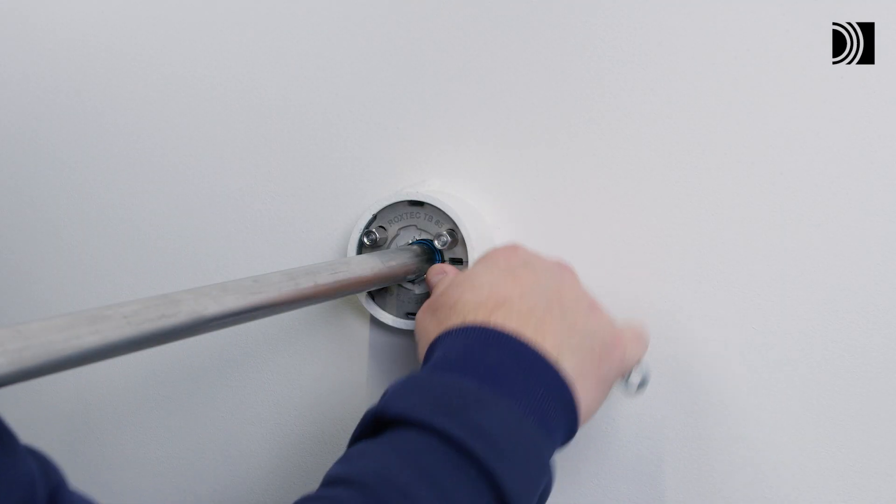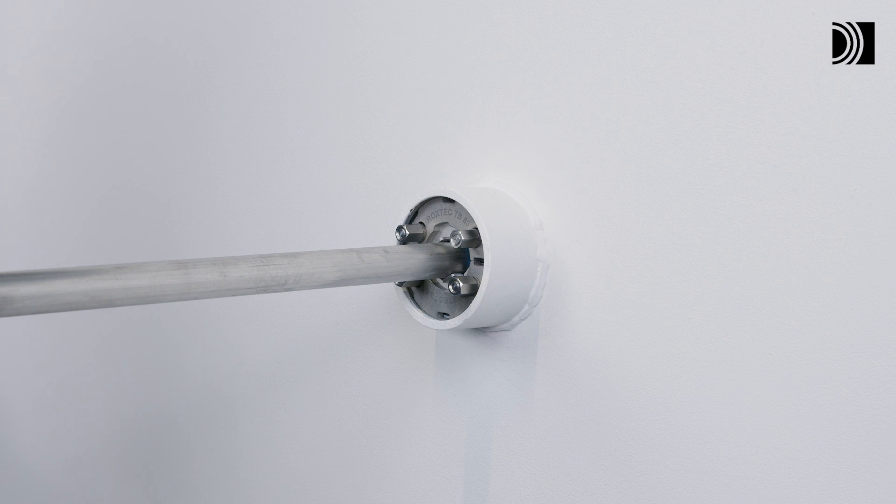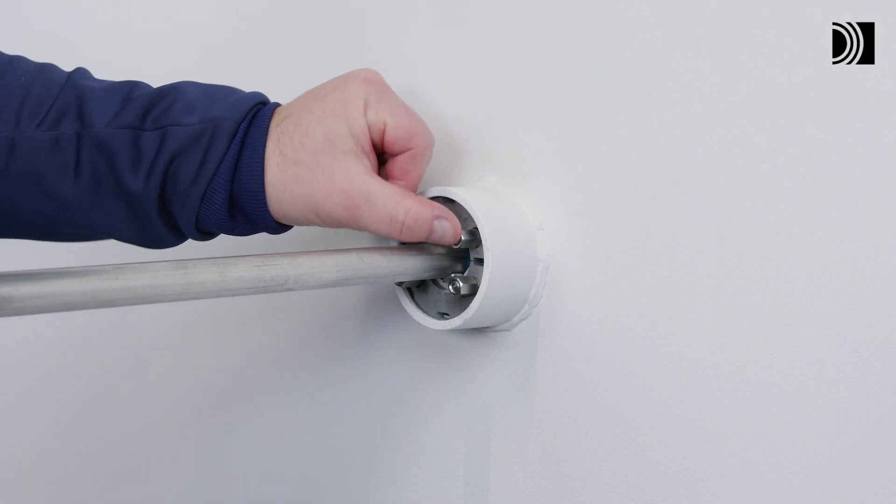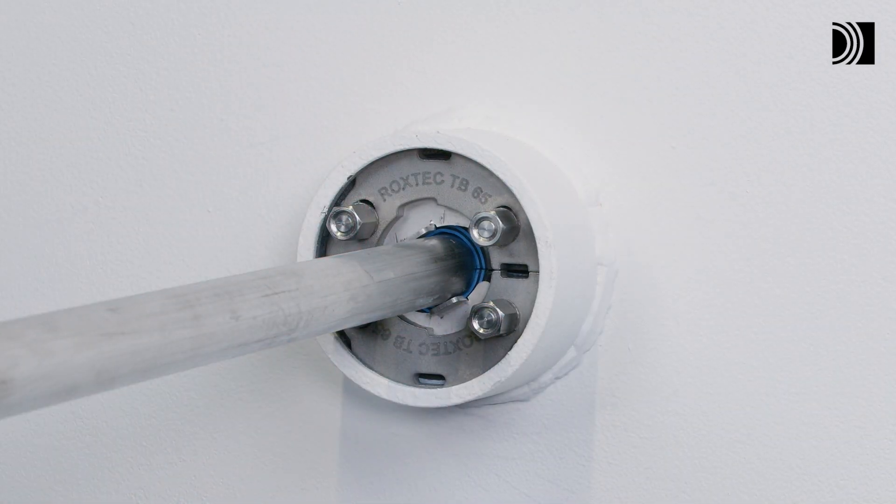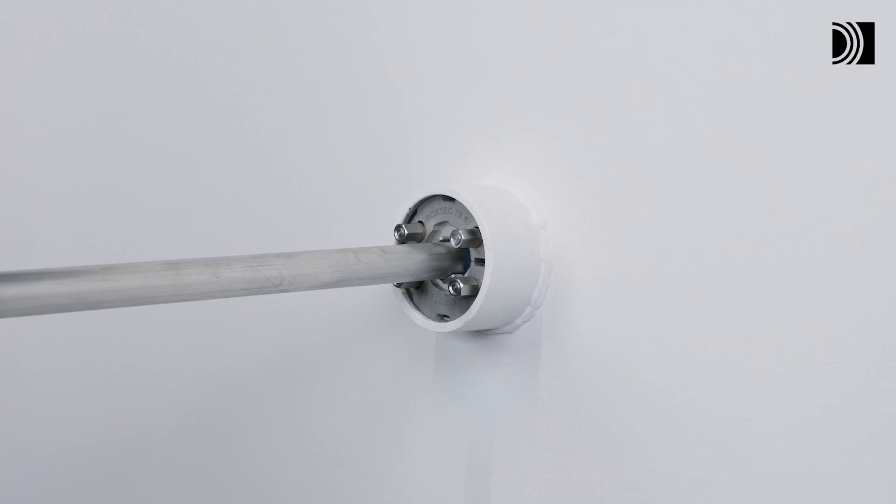Full compression is normally achieved when the end faces of the screws are flush with the end faces of the nuts. Excess protruding lubricant shall be visible and the rubber shall bulge. If not, further tighten the nuts.